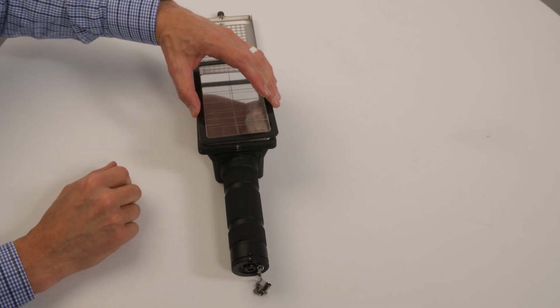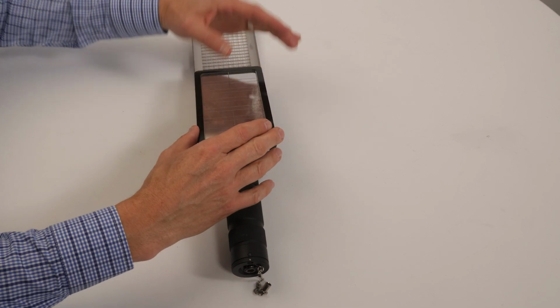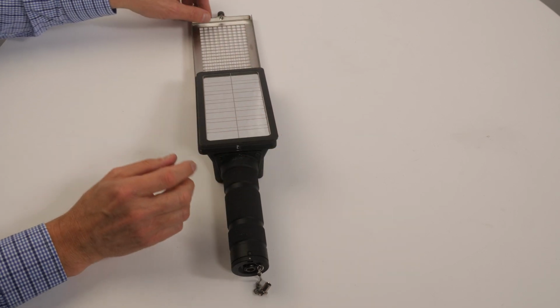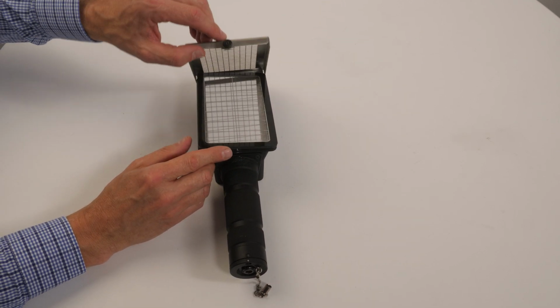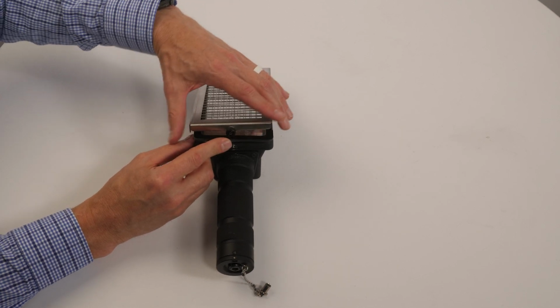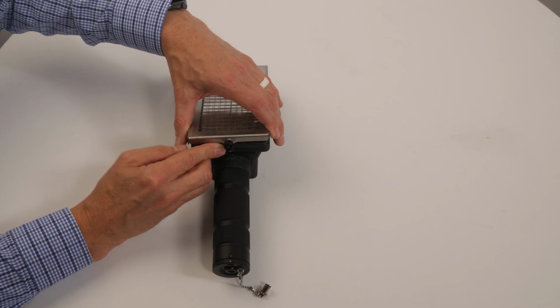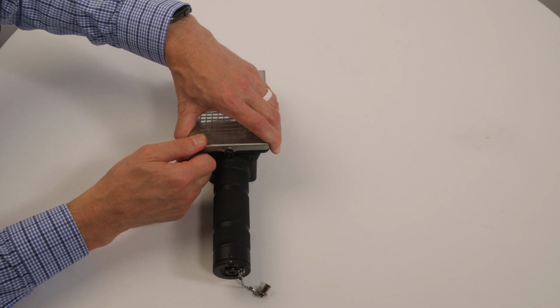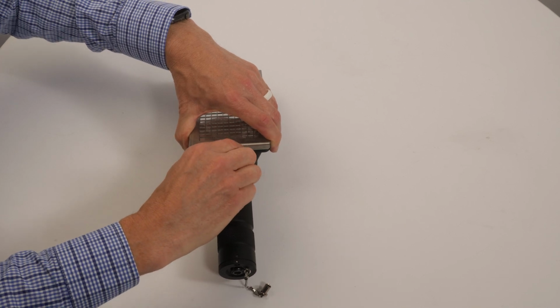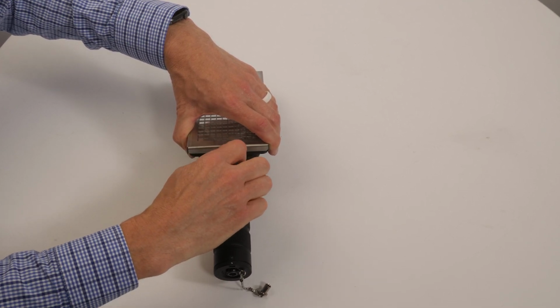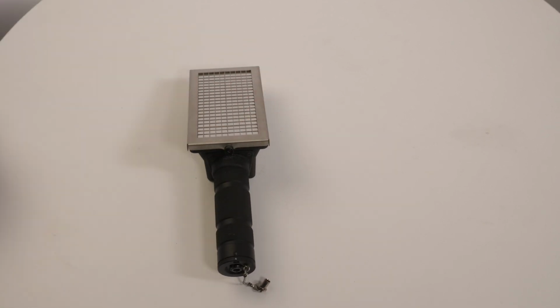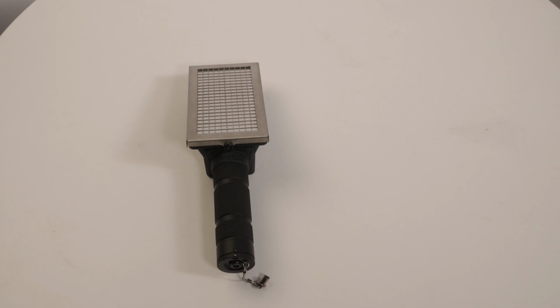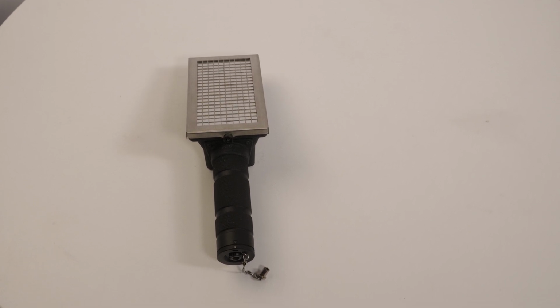The Mylar window and protective screen can shift when closing the protective grate and cause a light leak if not placed correctly. To place it correctly, close the hinged protective grate and apply pressure on the edge of the protective screen and Mylar window to hold in place while closing the protective grate. Ensure that the captive screw engages with the threads in the hole in the probe and tighten. Hand tighten only. Do not over-tighten the captive screw.